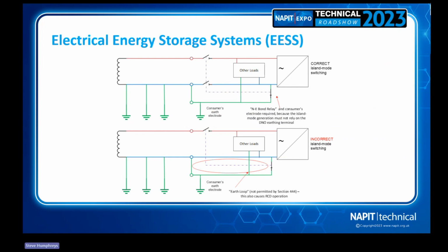So if you look at the top diagram, what you can see there is we've got a PME earthing system coming in, and the top one is correct. So you can just make out that the island mode, hopefully you're seeing that, that's our island mode isolator. That is open because it's gone into island mode. This consumer earth electrode is in there that we've put in, and then we can see here that our neutral earth bond relay is closed. So, let's imagine there's a break here in this cable on the PME, we've created our own TNS earthing system because this is sitting independent of anything coming from the grid, and we're not feeding backwards.